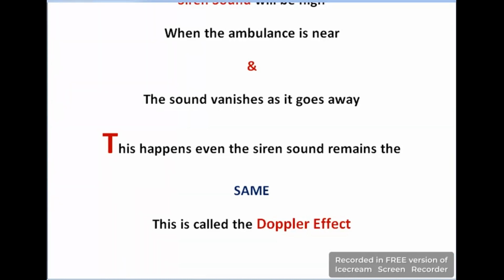That principle will be applied in this flow meter, as this flow meter is used where the fluid has particles in it. When a transmitter emits its radiation, these radiations will strike these particles, then reflect and go to the receiver. These particles will change their location during flow. So that will be according to the Doppler effect, as the frequencies will change with time.